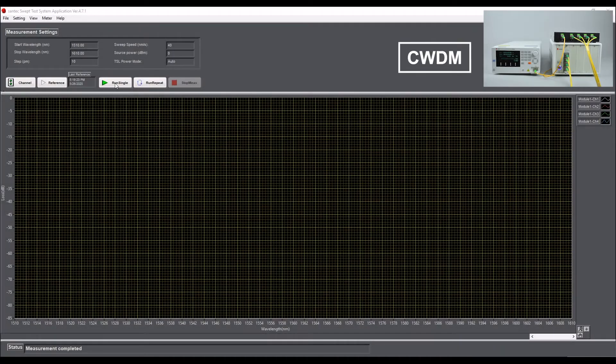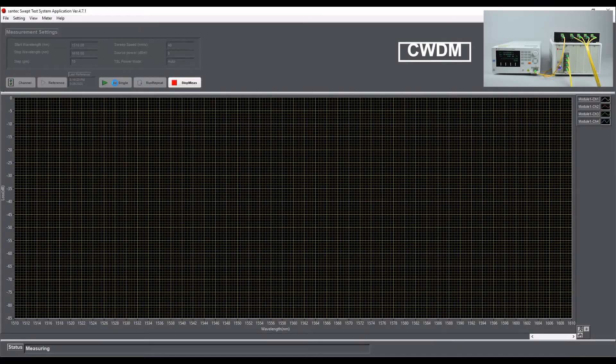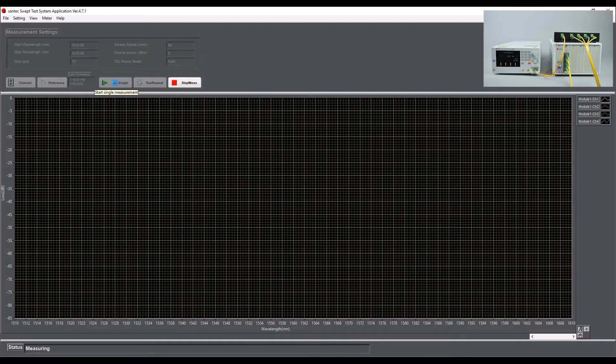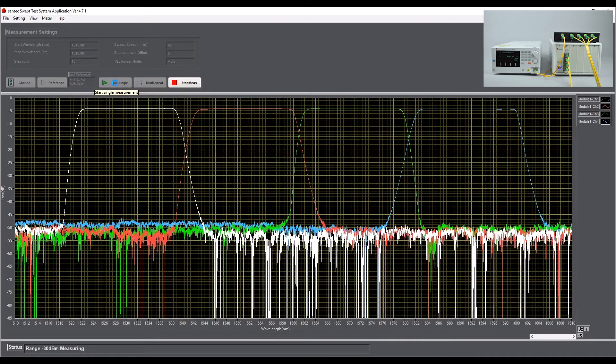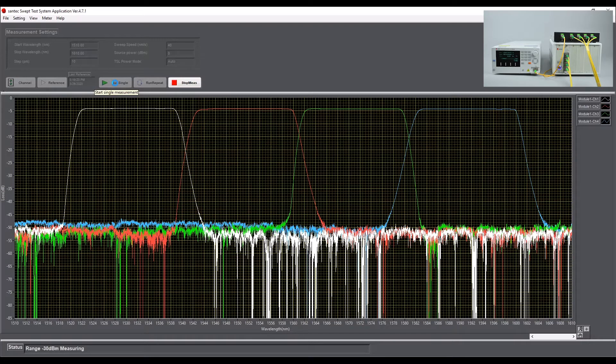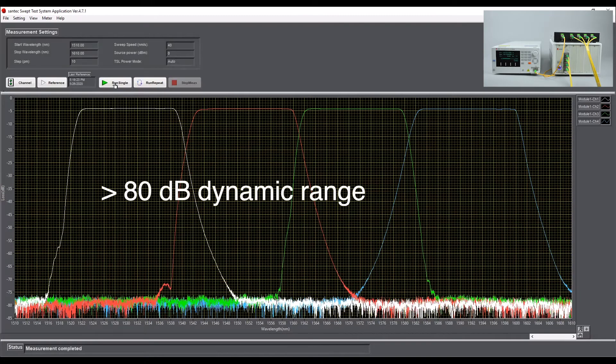Thanks to the large signal to noise ratio and the high optical power of the tunable laser, coupled with the wide dynamic range of the MPM power meter, it is possible to achieve more than 80 dB in dynamic range measurements.